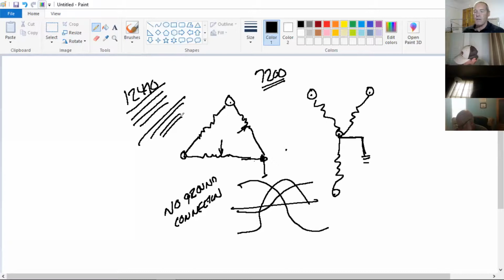Now, why do we use delta? There is a humongous use of it for one part of our utility system, and that's in transmission. As far as distribution is concerned, Professor V can attest to this, delta in distribution is going away. There's just not as much delta as there was on a distribution system, and the huge reason is this right here. I don't have a neutral or ground. Either I've got to have the customer supply one, or I've got to produce one to be able to have another safety feature going on here. Why do we use it in transmission?